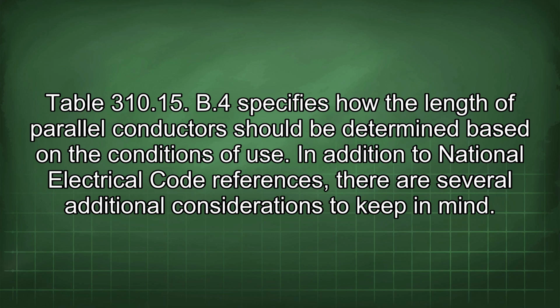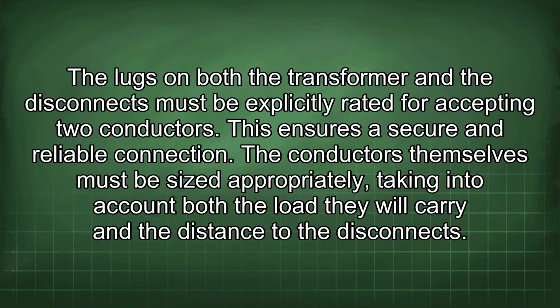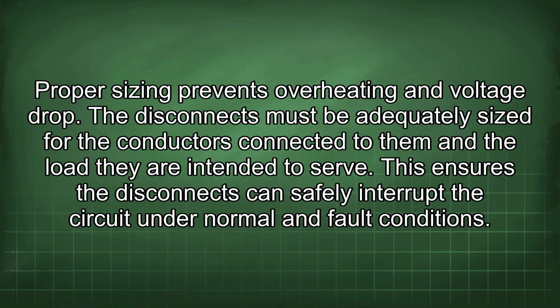In addition to National Electrical Code references, there are several additional considerations to keep in mind. The lugs on both the transformer and the disconnects must be explicitly rated for accepting two conductors. This ensures a secure and reliable connection. The conductors themselves must be sized appropriately, taking into account both the load they will carry and the distance to the disconnects. Proper sizing prevents overheating and voltage drop. The disconnects must be adequately sized for the conductors connected to them and the load they are intended to serve. This ensures the disconnects can safely interrupt the circuit under normal and fault conditions.